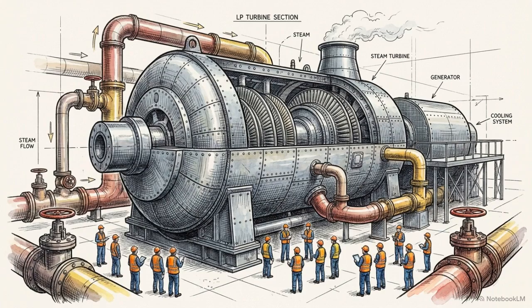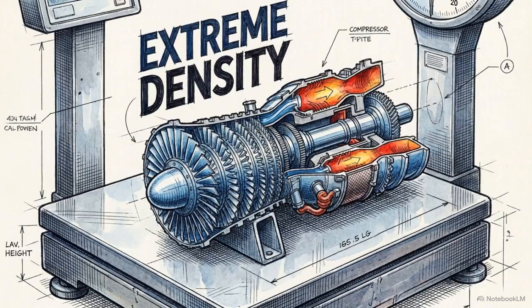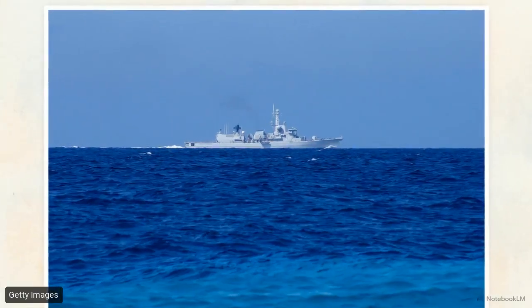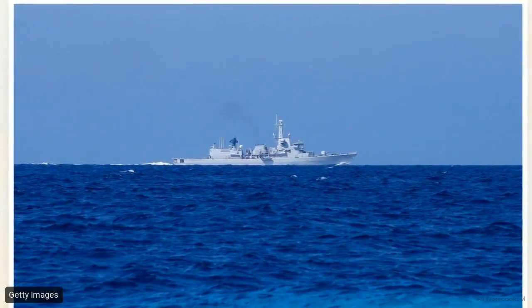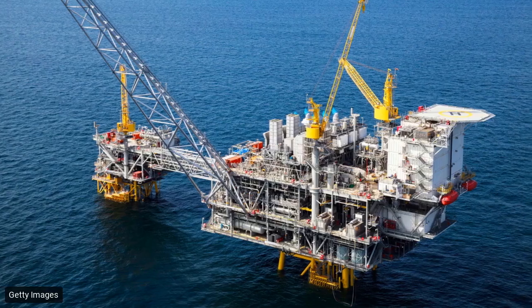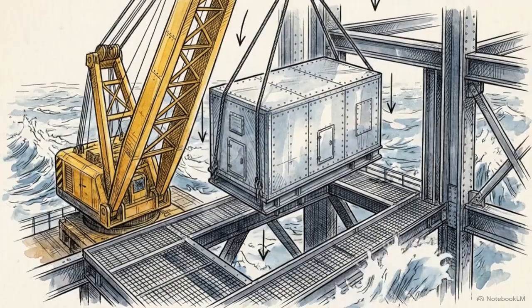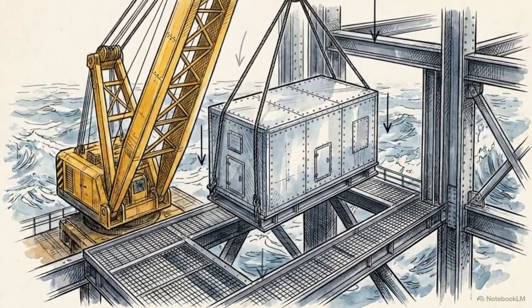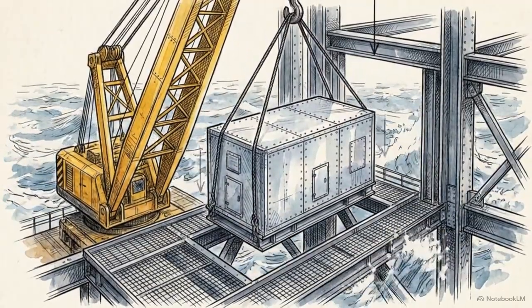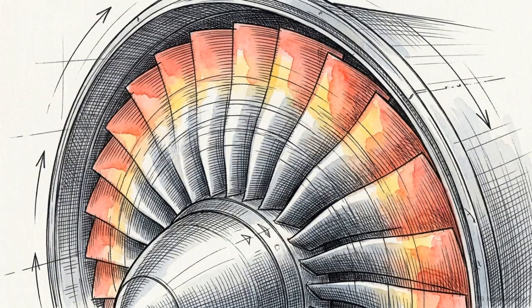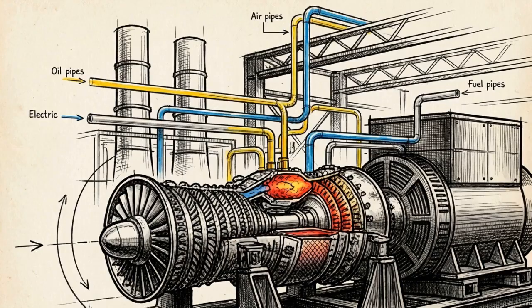Heavy-frame industrial turbines built for baseload grids can weigh hundreds of tons. This aeroderivative design trades that raw mass for a 30-to-1 compression ratio, making it the standard for naval applications and mobile power units where space is at a premium. You find these units on offshore platforms, where 30 megawatts of power must be squeezed into a package light enough to be craned onto a platform deck. Safely harnessing 10,000 RPM of continuous aviation power requires moving away from traditional mechanical intuition. Operating this machine is a matter of absolute precision in the management of its auxiliary lifelines.